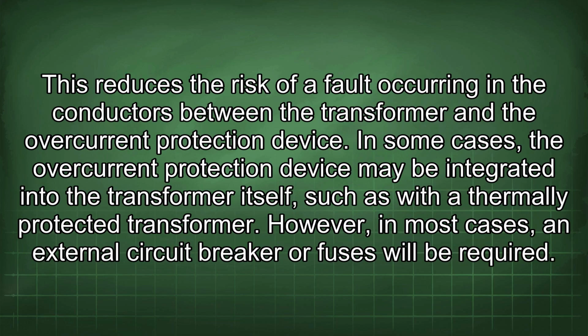This reduces the risk of a fault occurring in the conductors between the transformer and the overcurrent protection device. In some cases, the overcurrent protection device may be integrated into the transformer itself, such as with a thermally protected transformer. However, in most cases, an external circuit breaker or fuses will be required.